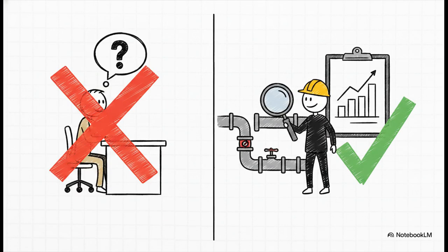But how do you actually find these source and route pairings in the real world? Well, I'll tell you what you don't do. You cannot identify hazards sitting in a conference room staring at a diagram, just relying on someone's memory of past events. You literally must walk the actual process on the floor. And you've got to cross-reference that with hard data, mining your environmental monitoring trends, your excursions, and past investigations. Completeness protects the strategy, because unnamed hazards absolutely cannot be controlled.